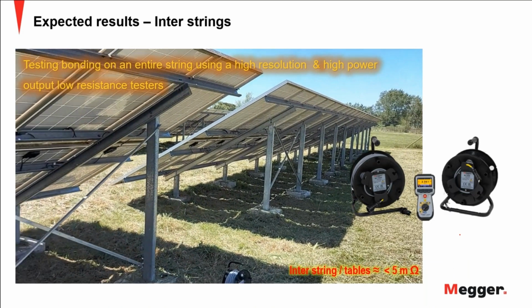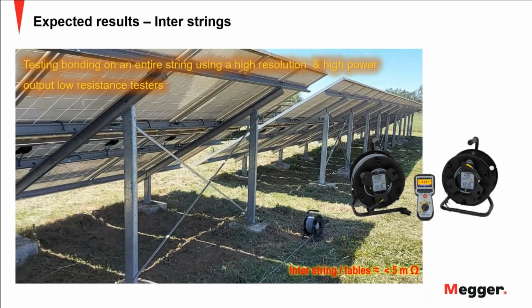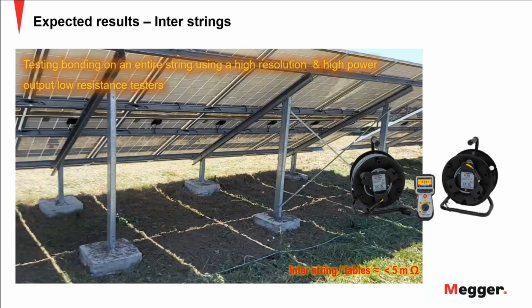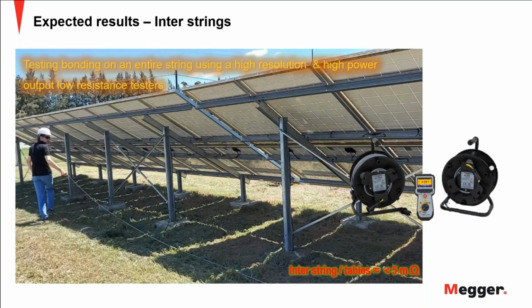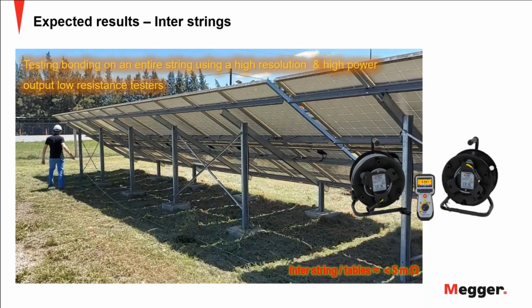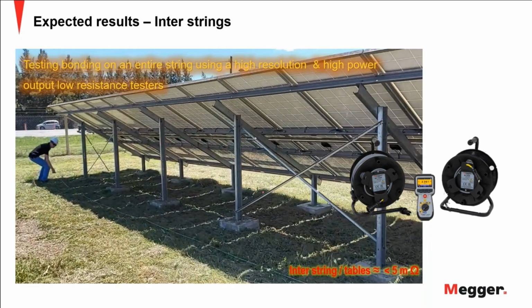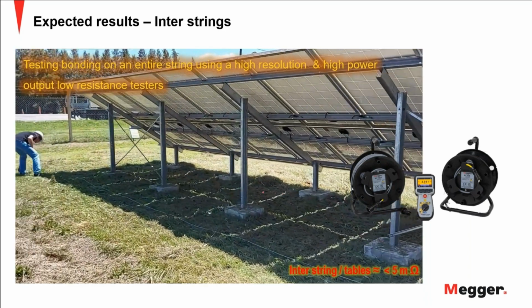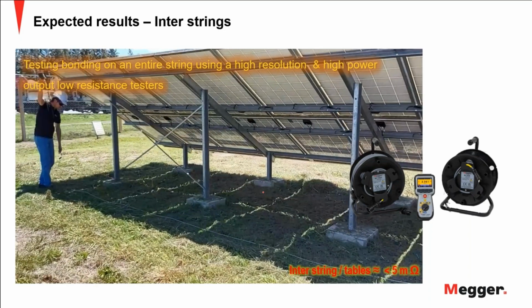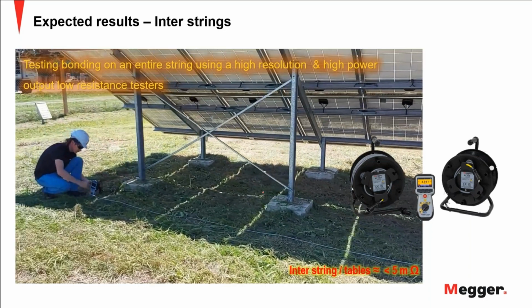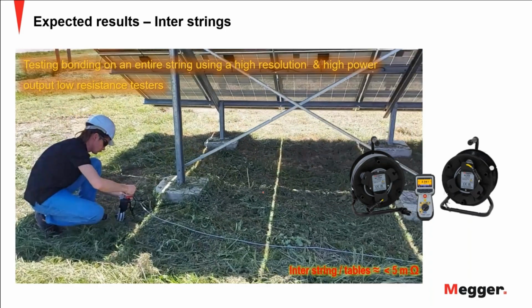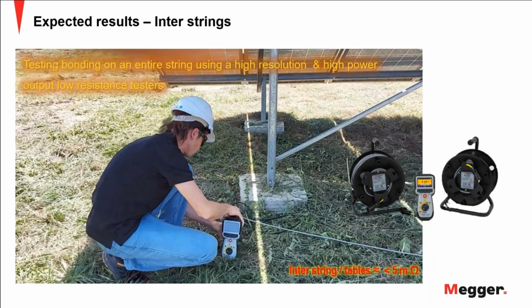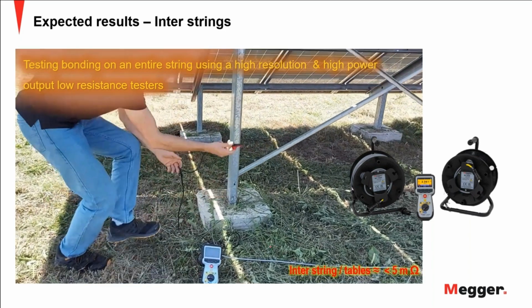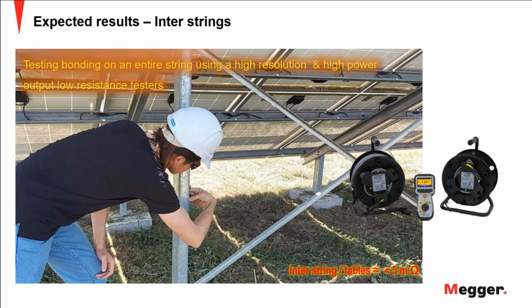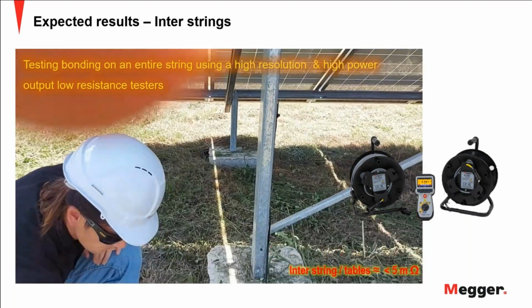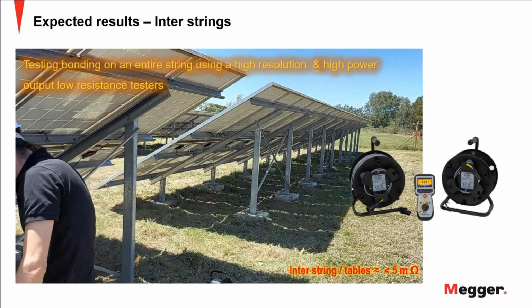And here, this video shows you that we have a reel at one end of the rack. We extend the cable, and then at the other end we connect the second lead, and next to it is where you perform the measurement. You can see that the instrument already has the other lead connected. Each set of cables has two wires, so you have the 4-wire measurement, and that's why it shows black and red, that clip there. And once both ends are connected, then you can run the test.